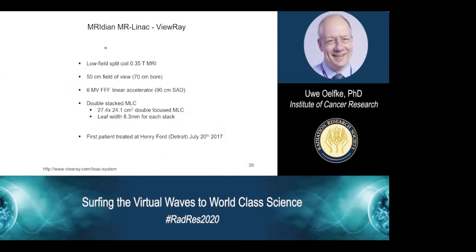And these are the parameters of the machine. As I said before, the low field split coil of 0.35 Tesla stays the same. The field of view, a 6 MV flattening filter free linear accelerator, and a specialty is a double stacked MLC, which is double focused. And the first patient with this device was treated in Detroit in 2017.